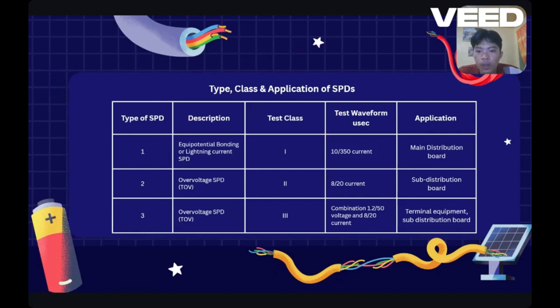So, type and class application of SPD. We have three types of SPD. We have equipotential bonding or lightning current SPD, test class 1, test waveform in microseconds 10 over 350 current. Then application is main distribution board.